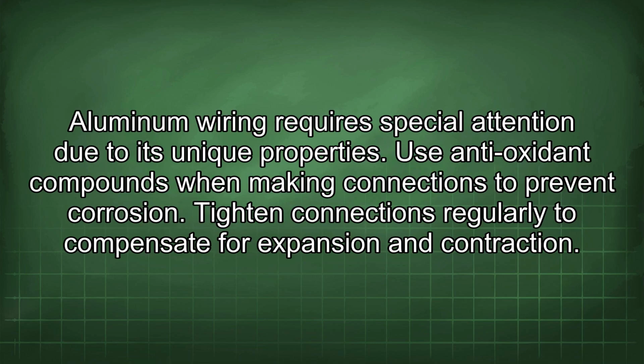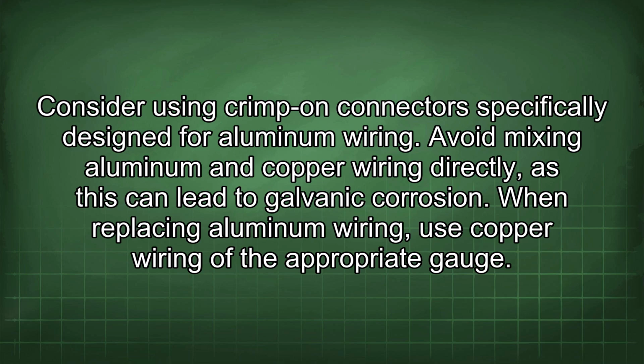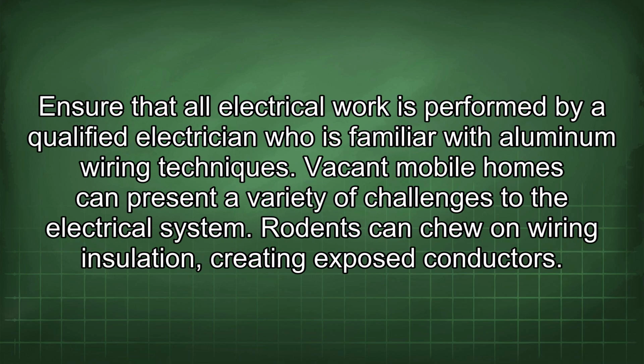Aluminum wiring requires special attention due to its unique properties. Use antioxidant compounds when making connections to prevent corrosion. Tighten connections regularly to compensate for expansion and contraction. Consider using crimp-on connectors specifically designed for aluminum wiring. Avoid mixing aluminum and copper wiring directly, as this can lead to galvanic corrosion. When replacing aluminum wiring, use copper wiring of the appropriate gauge. Ensure that all electrical work is performed by a qualified electrician who is familiar with aluminum wiring techniques.